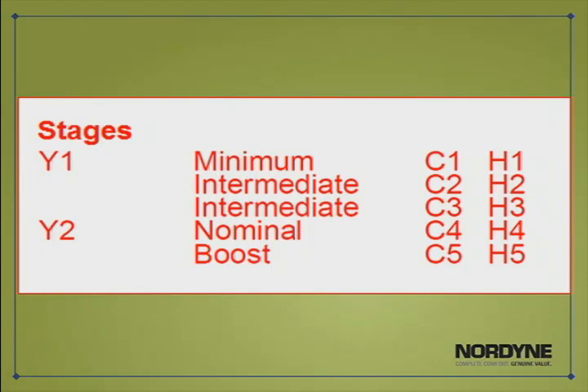The outdoor fan motor will start and run for 1 minute prior to the reversing valve being energized, and then the compressor starts. In most cases, the unit will start at stage C2. With a Y1, Y2 input, the condenser will run on stage C4 for 45 minutes. If the thermostat is still calling after 45 minutes, the system will go into boost mode, stage C5.